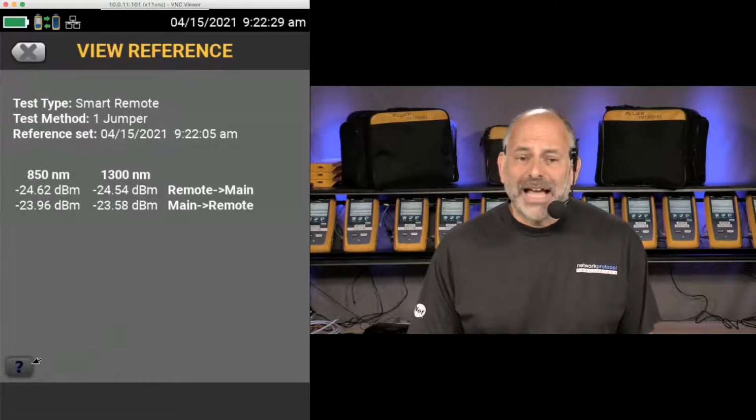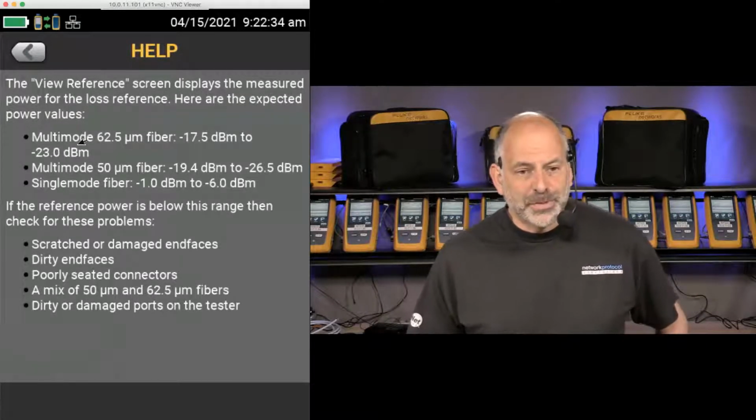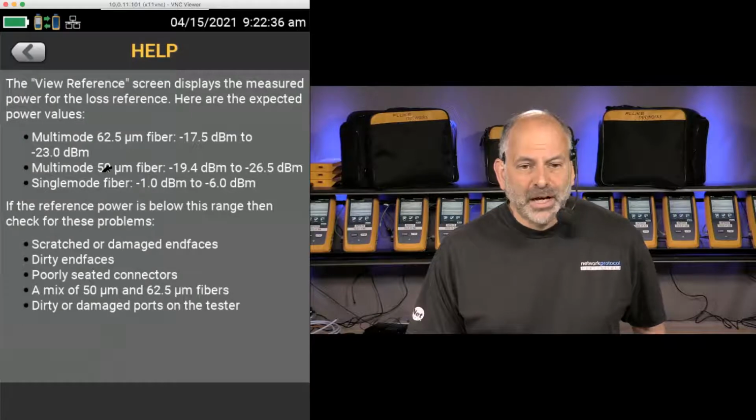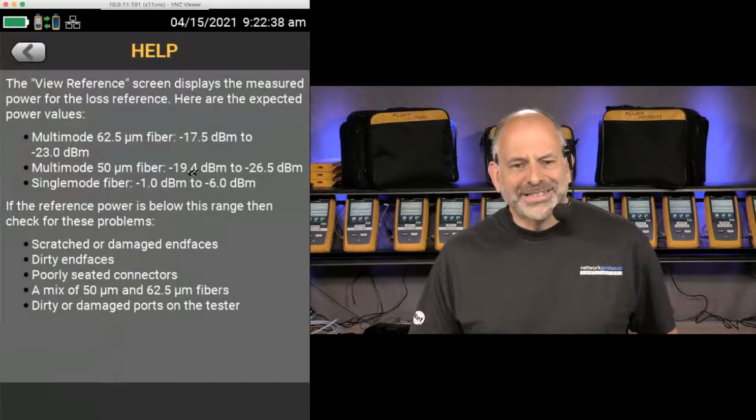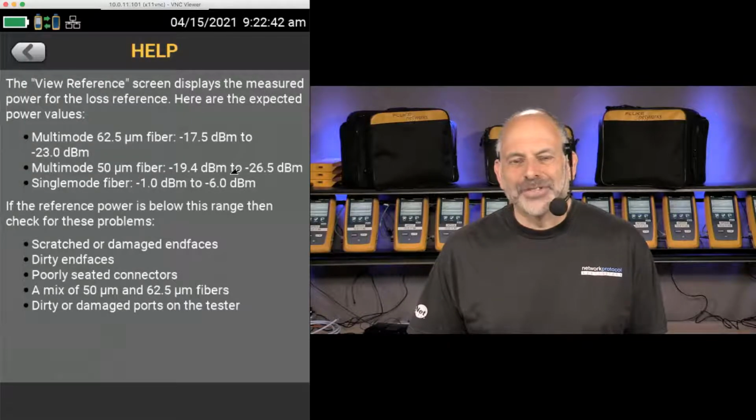If I forget what that range is, I can come in here and hit this question mark and it shows me right here for multimode fiber, 50 micron. Here it's listed as 19.4 to 26.5. I like 23.5 to 25.